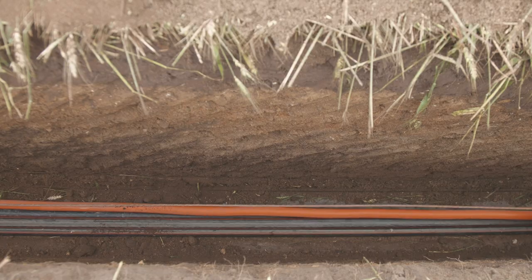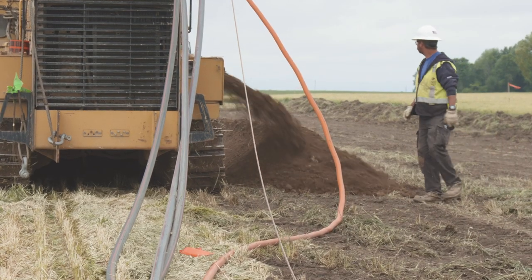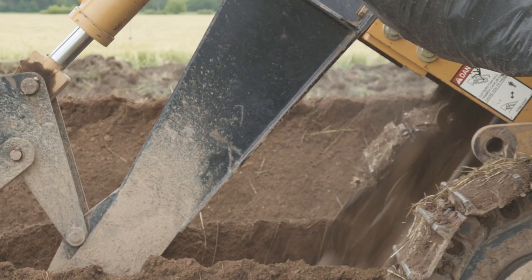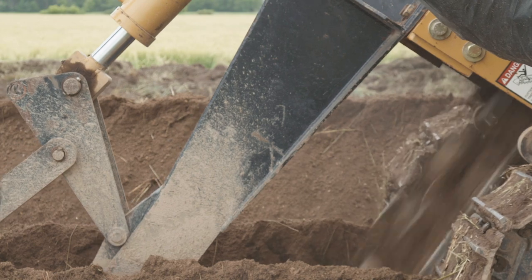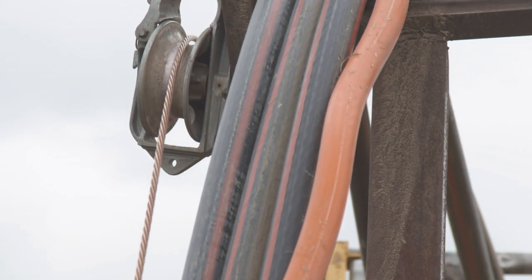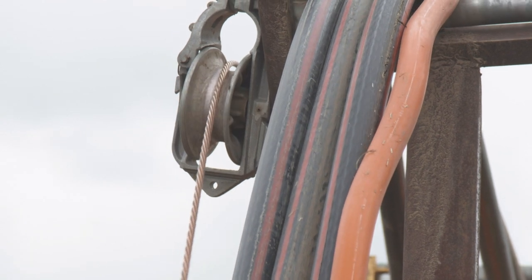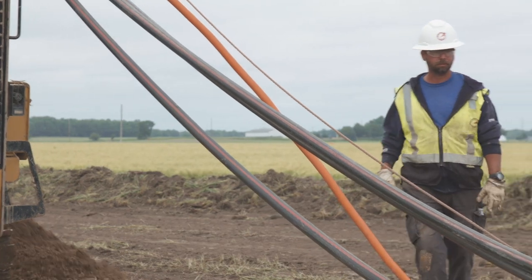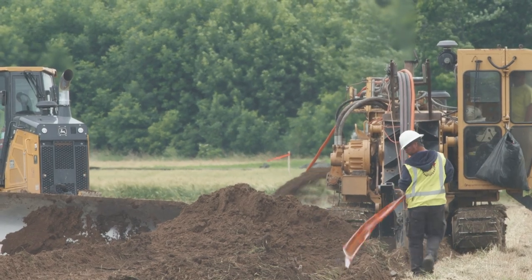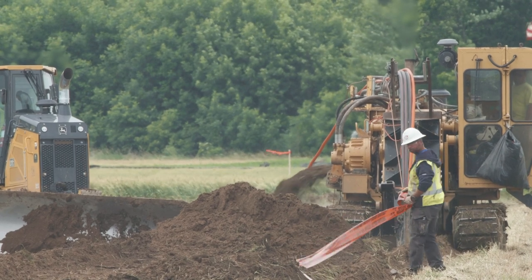The collector line is the main transmission line. We all see the power lines that come from an electrical pole to our house — that's what powers buildings. But all the electrical wires here are underground. The collection system is the cables that run underground from tower to tower — typically anywhere from 10 to 12 or 13 towers per circuit — and all those individual circuits go to the substation, where power is put out onto the grid.